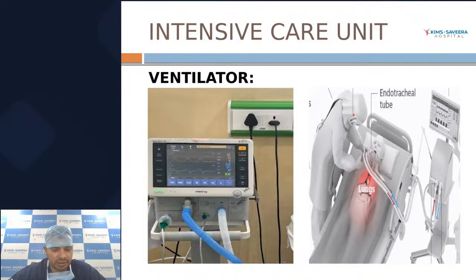This is the original ventilator machine, and there will be settings on it. We first check the weight of the patient, and based on his weight, we decide how many ml of gas exchange should be done. Suppose the patient is 60 kgs, then we set 6 to 8 ml per kg of body weight, so ideally around 360 to 450 tidal volume. Tidal volume is the amount of air pushed in a single breath. Along with that, we also set the rate, as to how many times in a minute they should breathe. This machine is very, very essential.